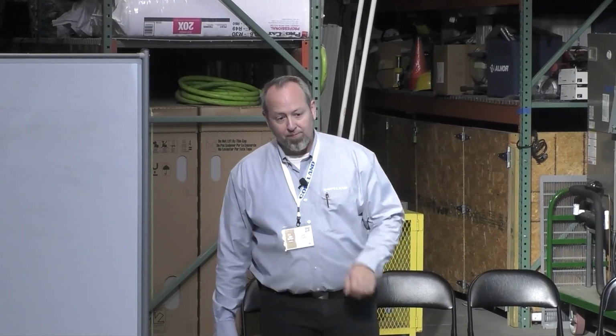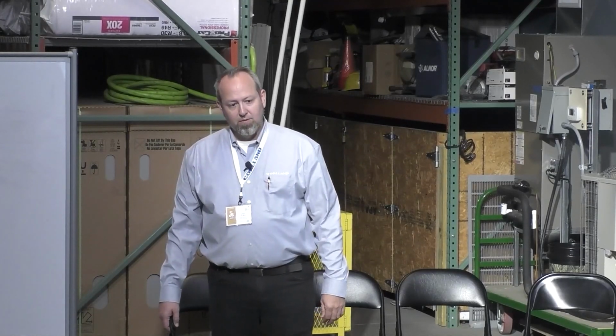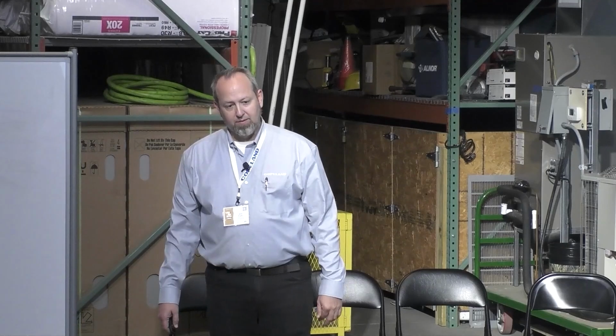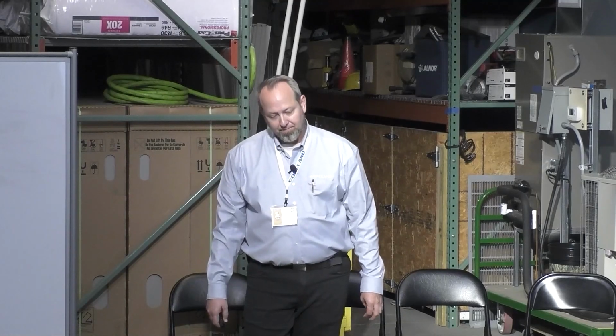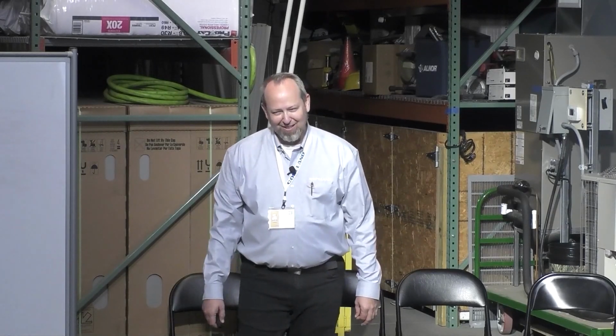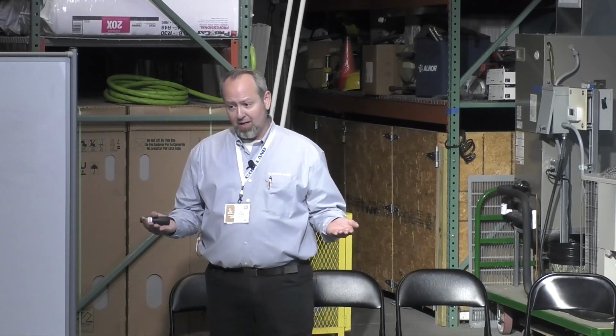Next question. If you have a multi-stage heat pump on your gas burner, what is your realistic airflow? You want about 350 to 400 CFM per ton in cooling. On heat mode, you want to be a little bit lower than that? Is there the same type of rule you can look at for first stage of the heat pump? A lot of what we do, you can set the exact CFM on the various heat stages right from the thermostat. So is there a rule we can use for knowing exactly where you need to be on first stage versus second stage of the heat pump?